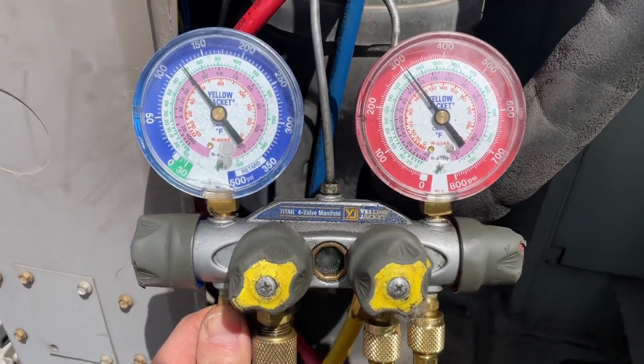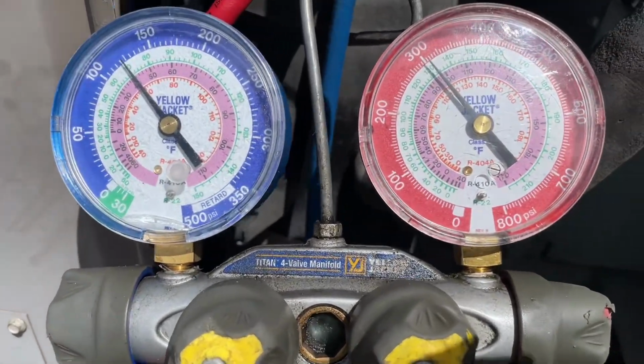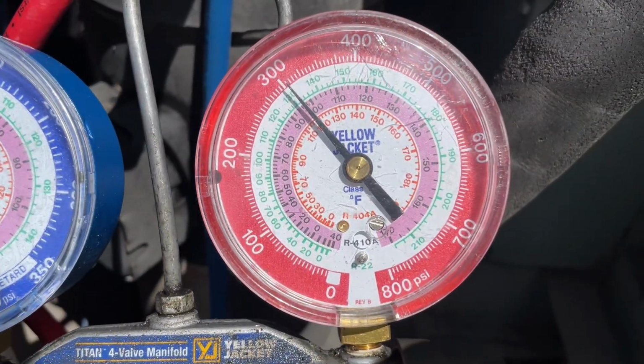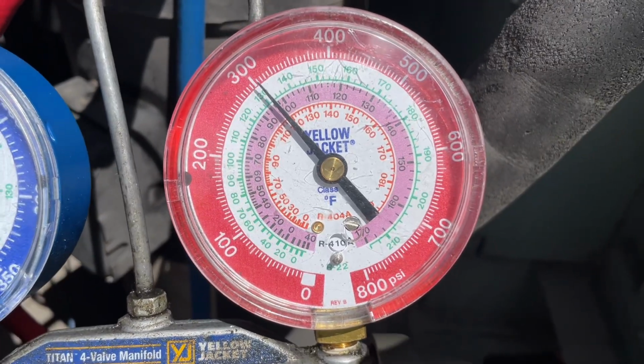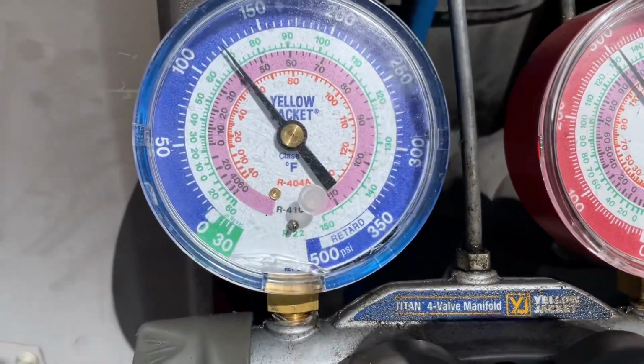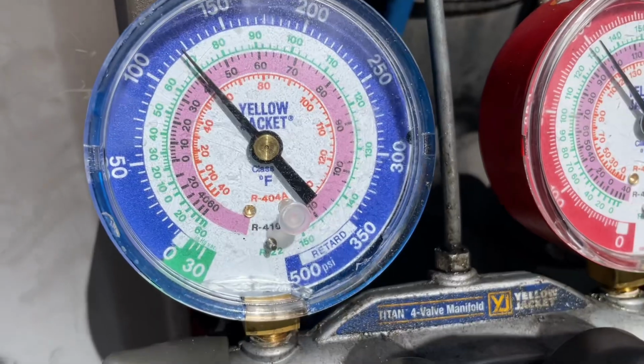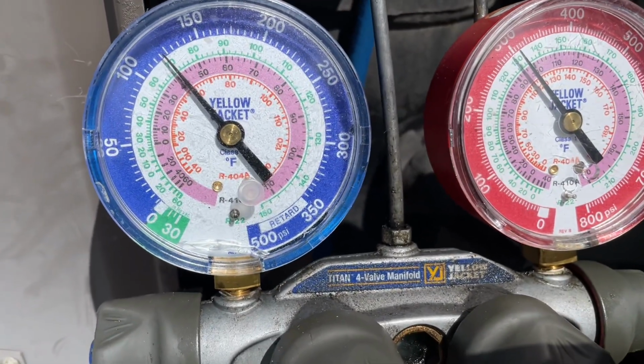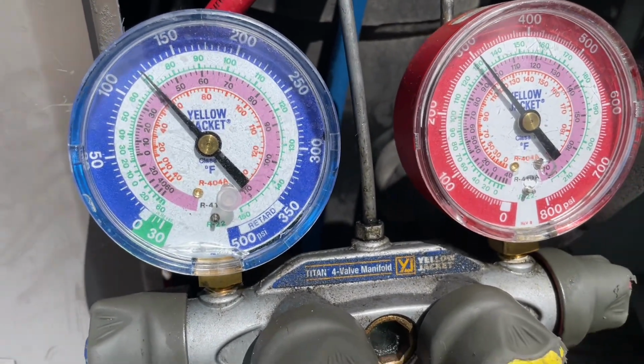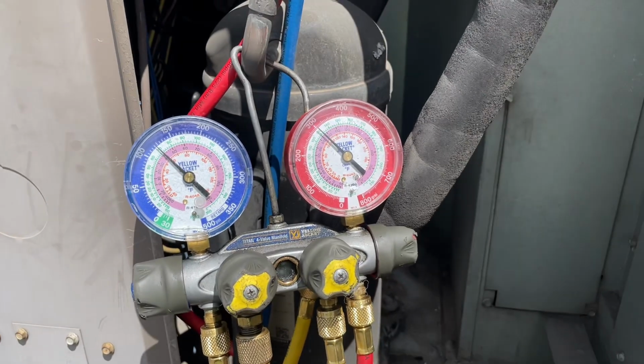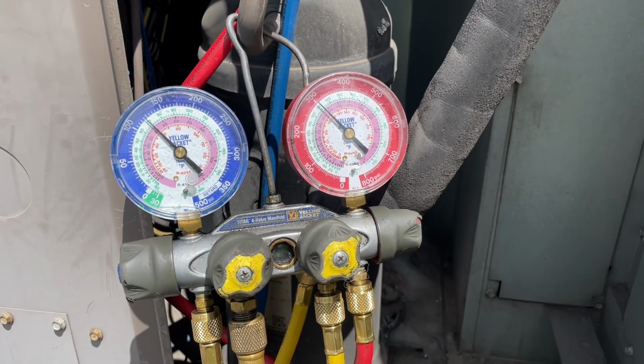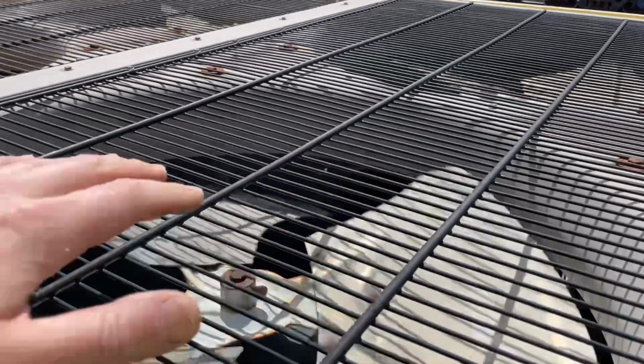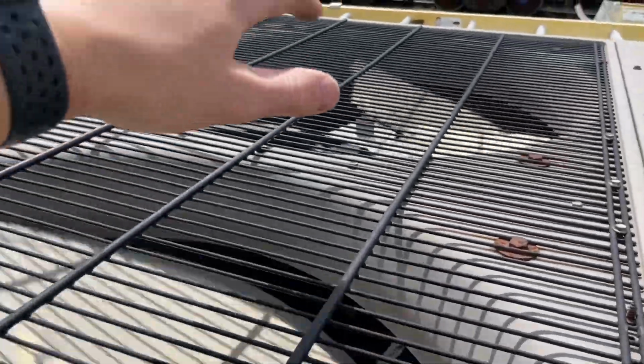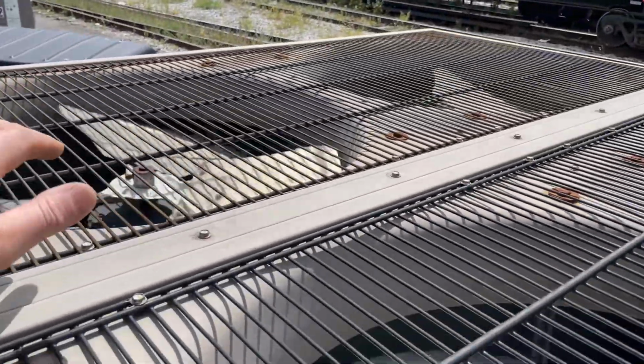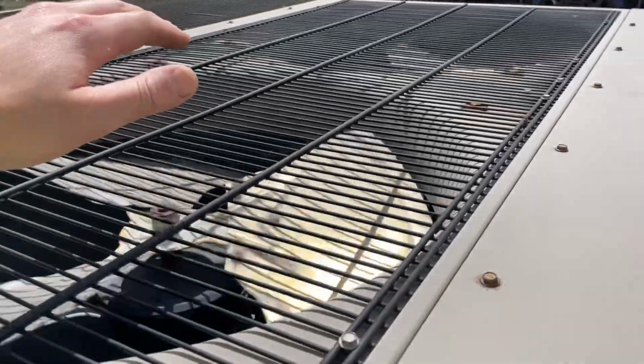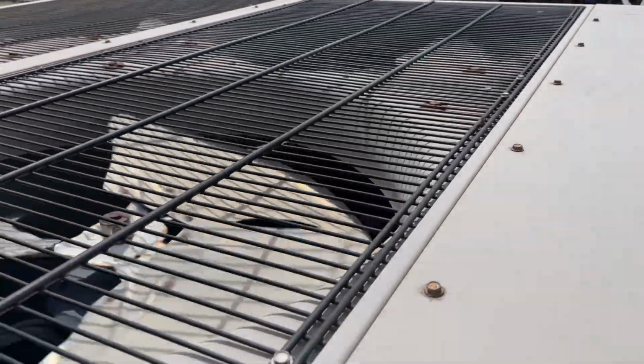And here's our second stage compressor pressures. 300 head, close to 100 degree condenser, and we got 125 suction pressure low side, about 42 degree evaporator. Both compressors are running awesome. We'll quickly check the condenser fans and we'll be out of here. All right, condenser fan 1, 2, 3, and 4 are all operating. I think this service call is all taken care of.